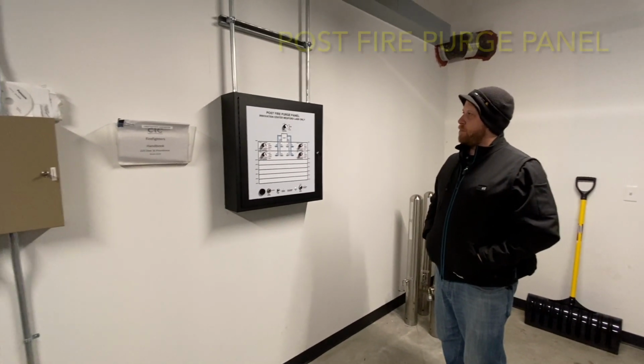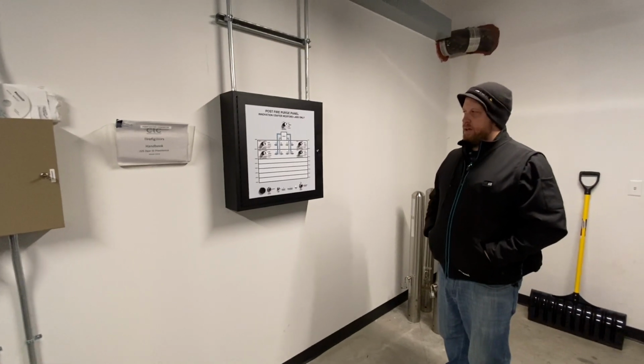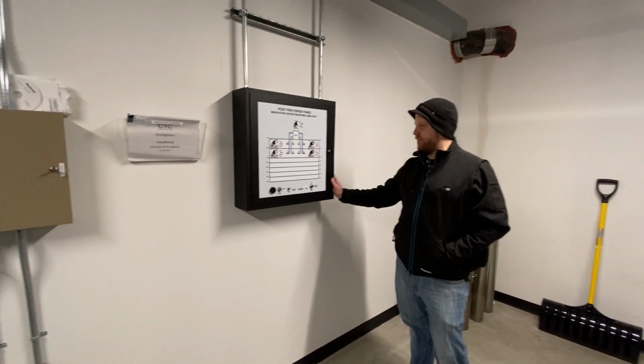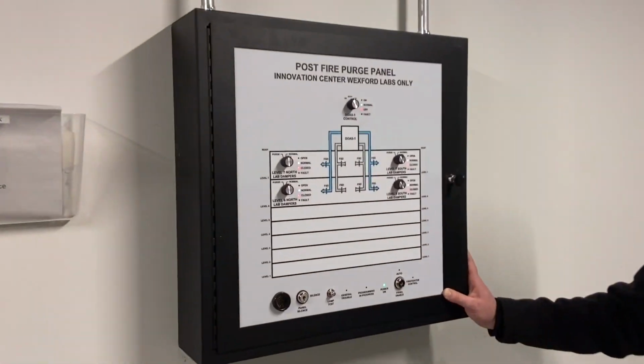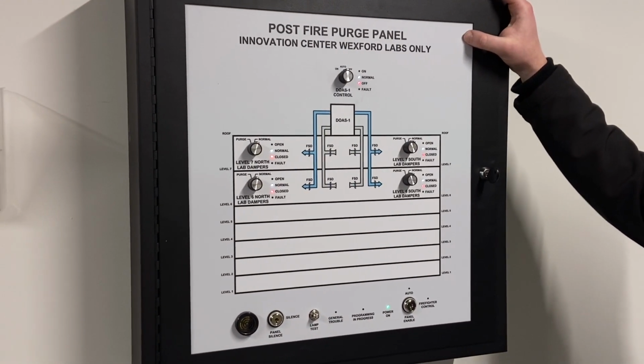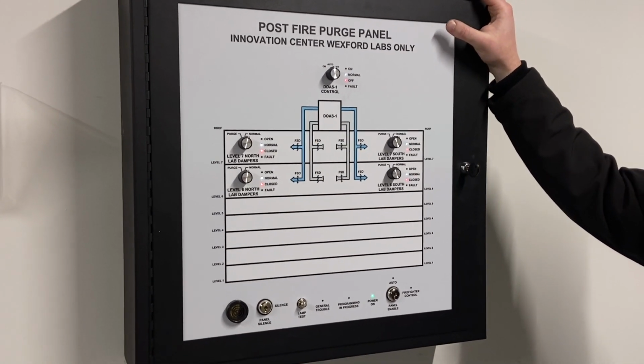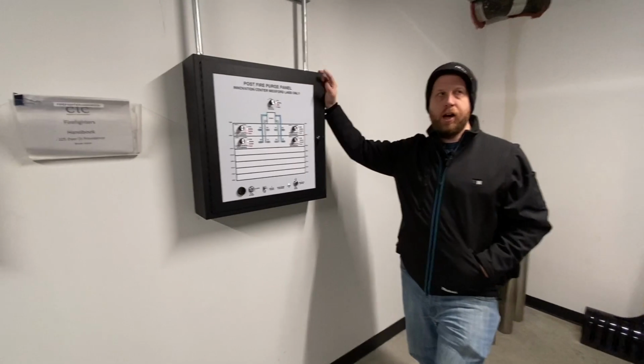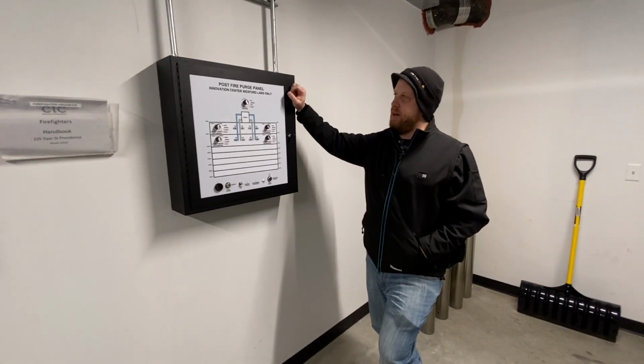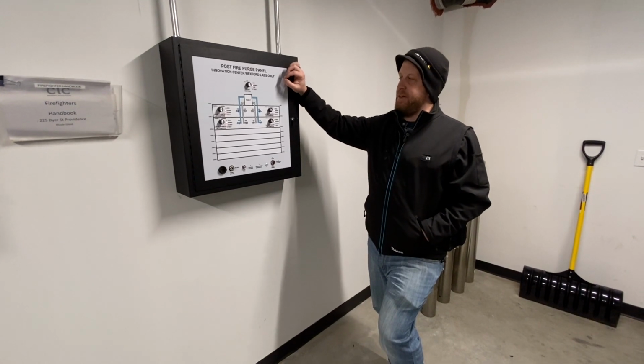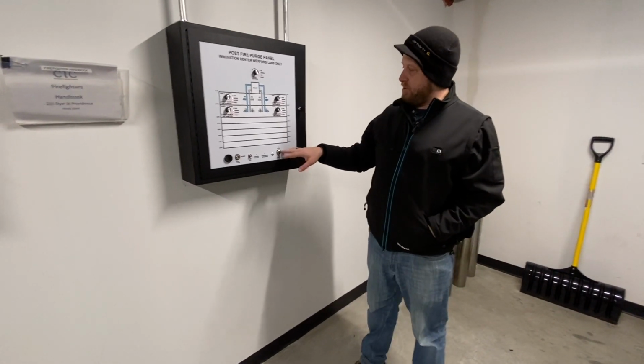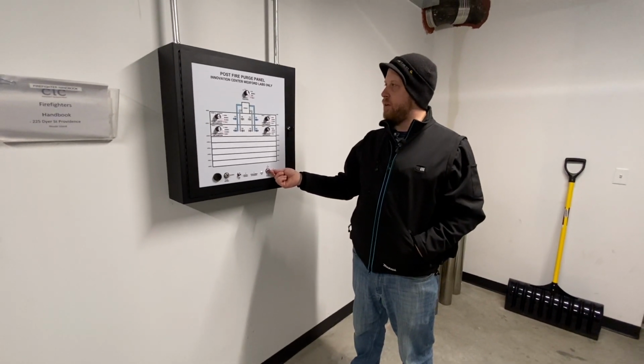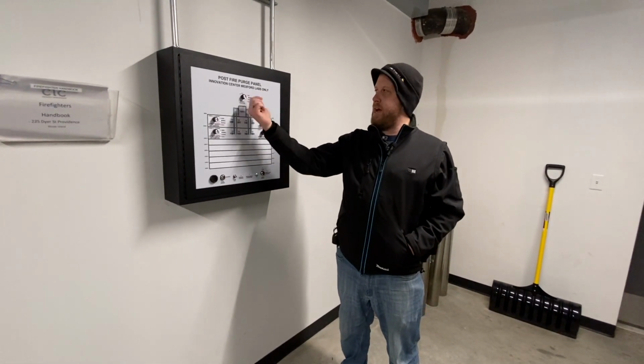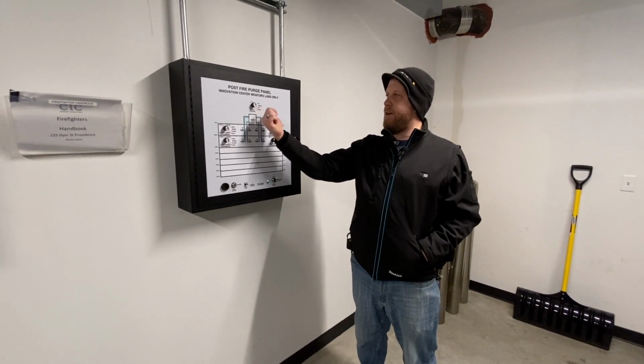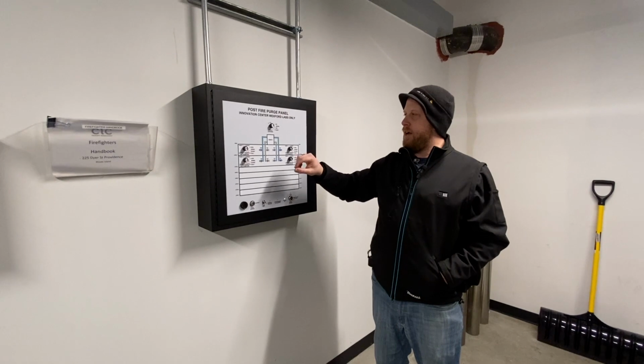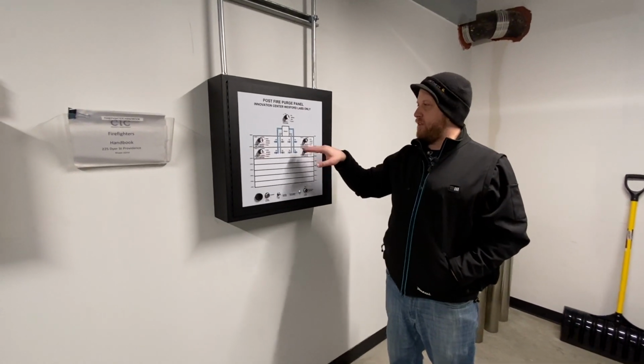So this is our post-fire purge panel. We got this made by a vendor of ours, but what this pretty much does is it's an override for any fireman or somebody who doesn't have access to the front end. A lot of this functionality you can do from the front end too, but what it's meant to do is the firefighter comes in here, turns this into firefighter control, and then they can manually turn DOAS 1 on or off. So they'll turn DOAS 1 on, and then they can purge specific zones.